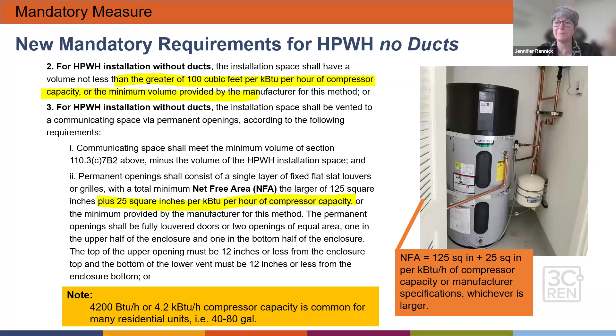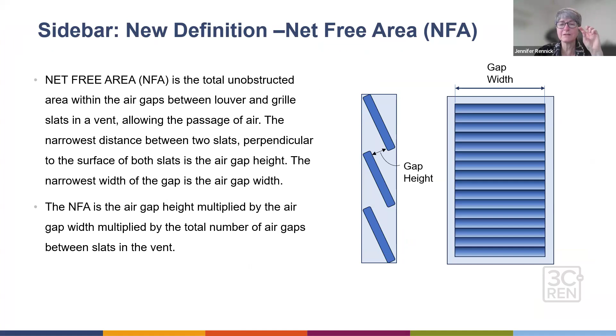A little sidebar on how to calculate the net free area. If you have a louvered door, you need to look at that. The quote-unquote gap height is the space between those louvers. And part of these mandatory measures, if you have a system with ducts, they're now specifically calling out that the penetrations at the ceiling or the wall are sealed and that the ducts themselves have R6 insulation.